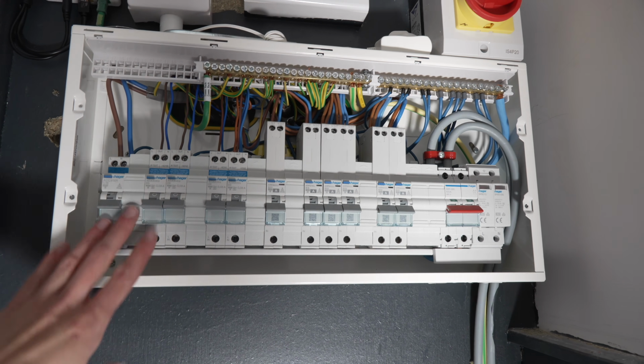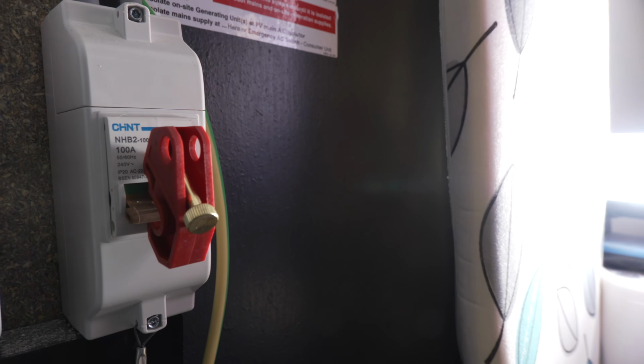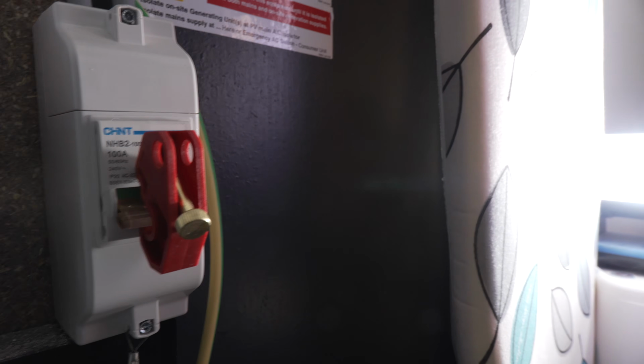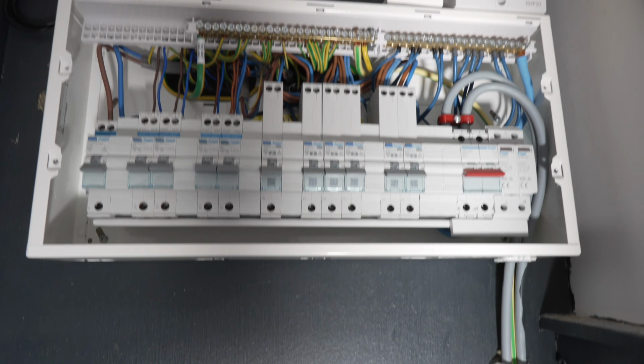And there we go, that's everything now fully locked off and isolated, so the board's isolated here, everything's turned off. And I've also locked off the double pole isolator at the incoming supply as well. It's worth doing that, don't risk these things. That double pole isolator is very much at knee height, and if you lift it up, that turns it on, so the last thing I want is to get caught on something and accidentally turn it on, so locking it off is a lot safer.